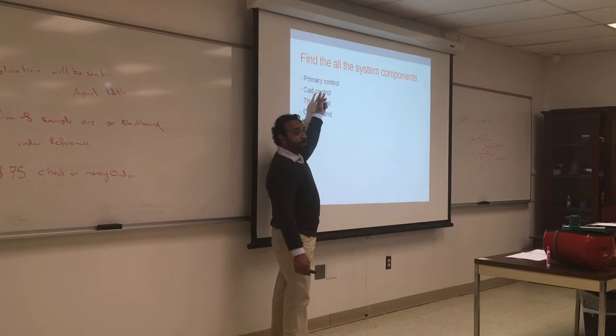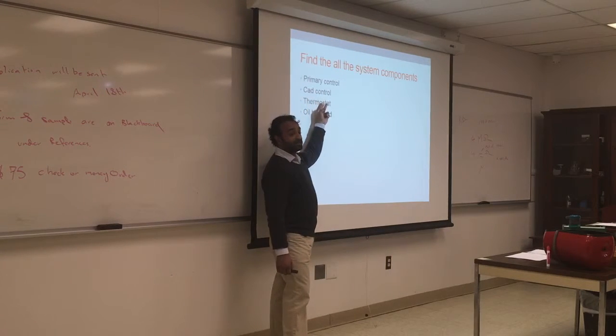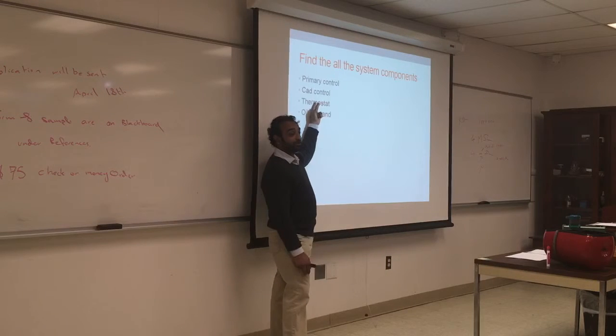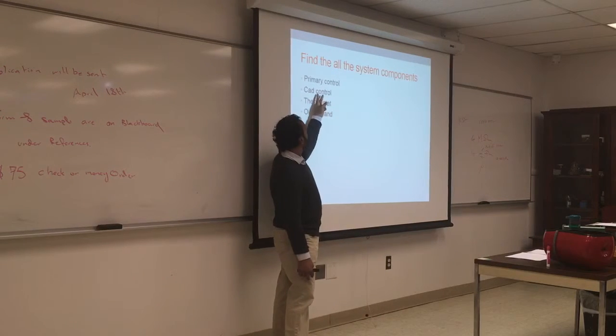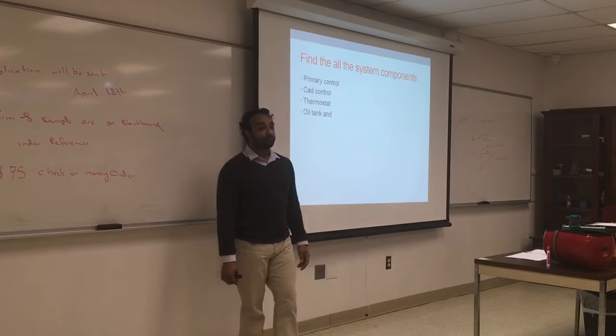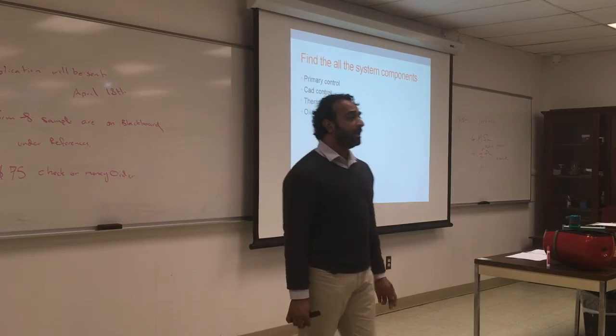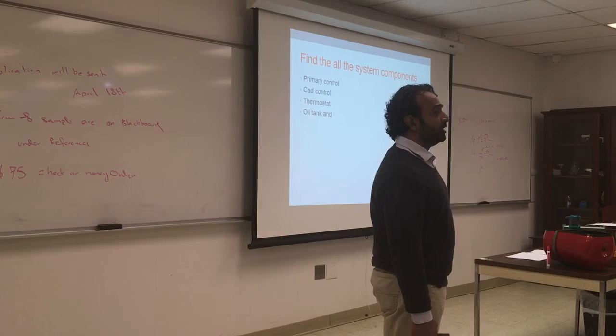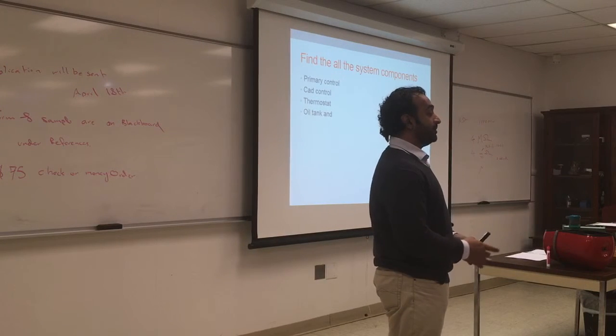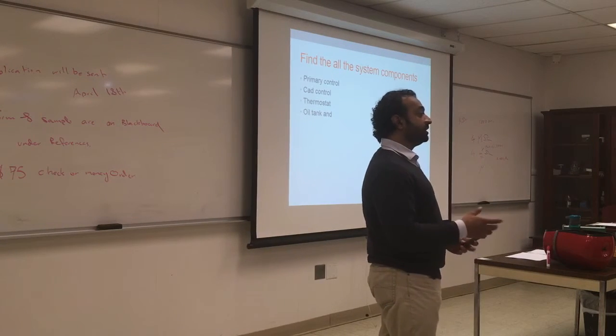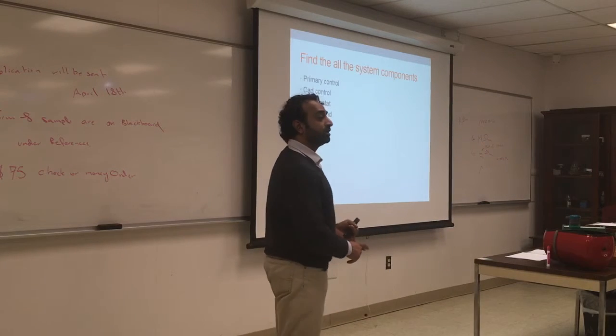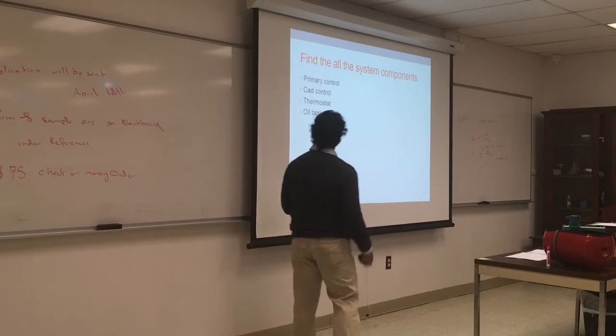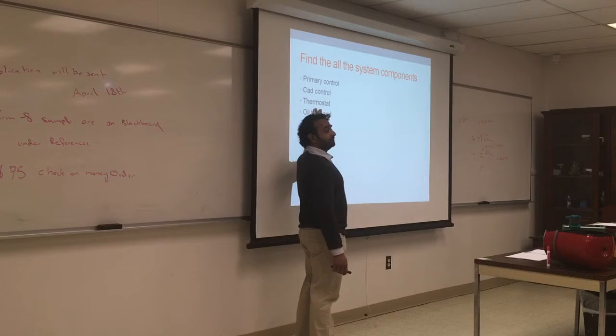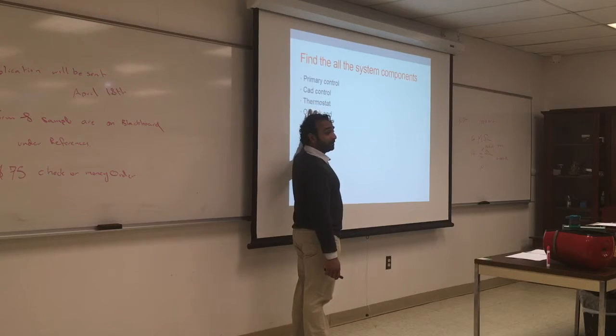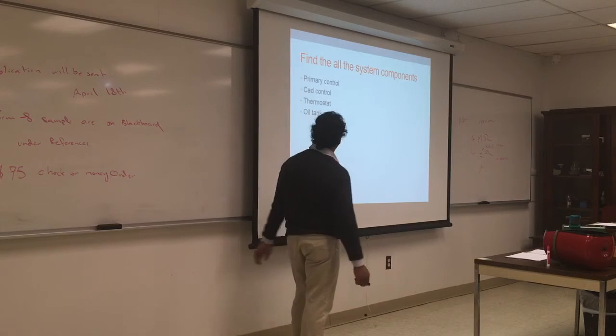So to find the primary control, you'll be surprised, sometimes it's not really close to where the burner is. So it is possible. And if you go into the European style burners like Viessmann's or Riello, everything is in the primary control. It's a whole cartridge you plug in. It has the ignition, it has the electrodes, it has the cad cell, it has everything in it. Find the thermostat, either one or two, make sure it's only one, not two, and if it's two, look further, and follow the oil tank and piping.